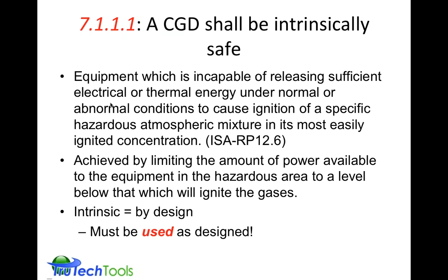Something to be really closely aware of is intrinsic really means, in this case, by design. So that emphasizes the product must be used as designed. Some products say must be used with a certain type of battery or equivalent. If you don't follow that procedure, you may be taking it out of its design criteria and no longer having it be intrinsically safe. Or it may require you to use it with the covers on and covers screwed down. That is an intrinsic or by design element, so you do have to comply with that in order for it to be intrinsically safe. So it's not just the product by itself, but it's how you use the product that has impact here.